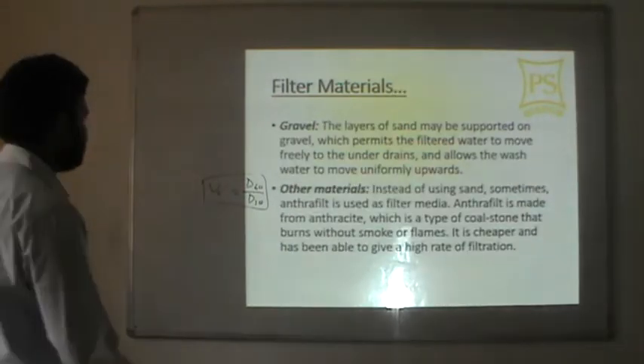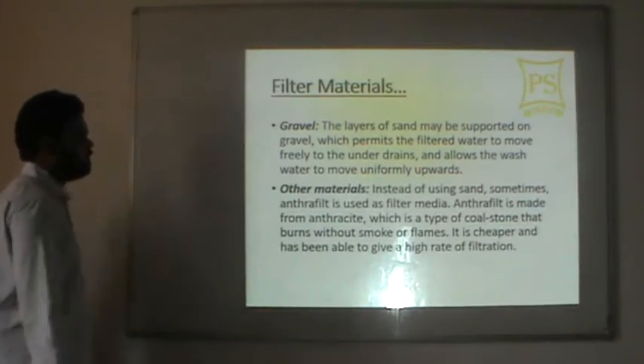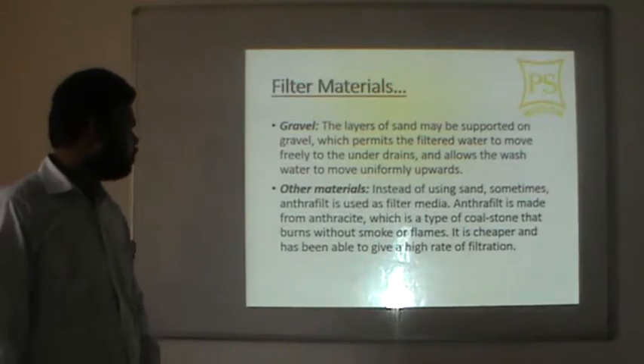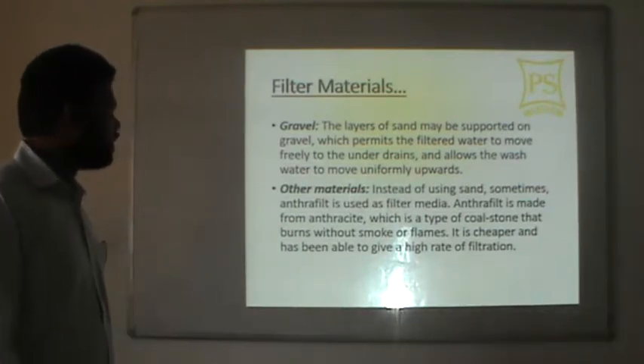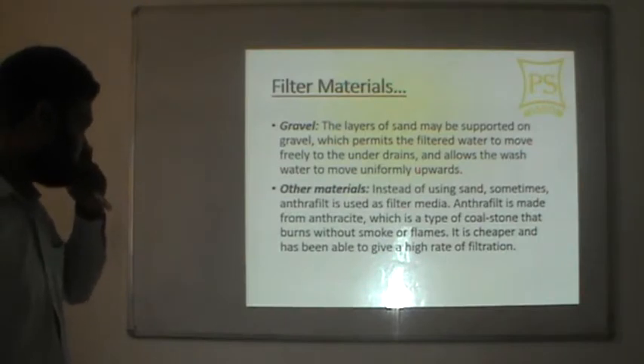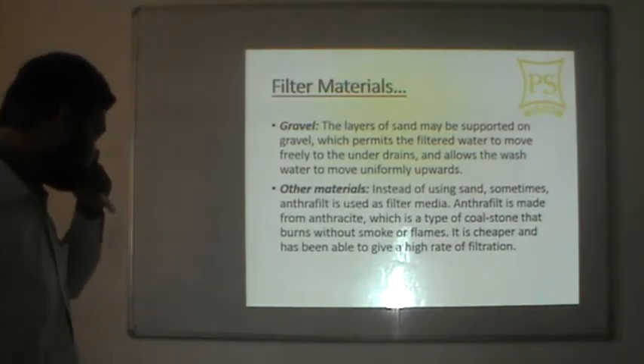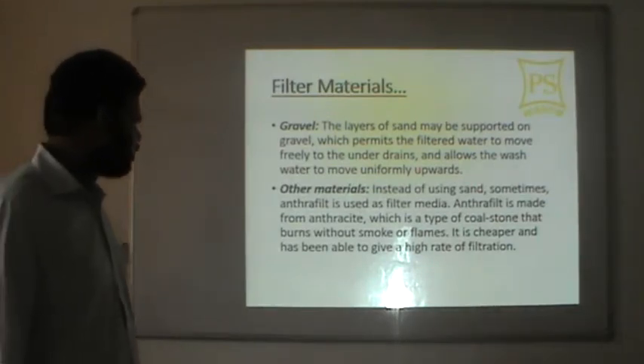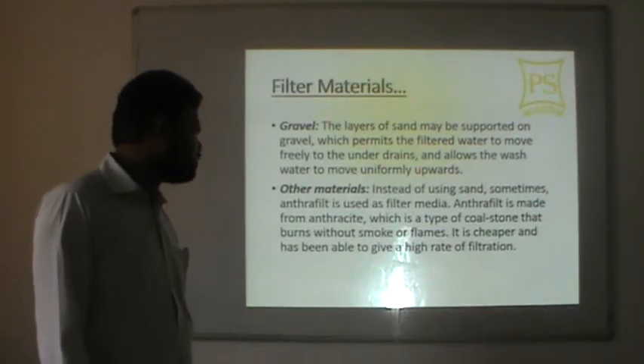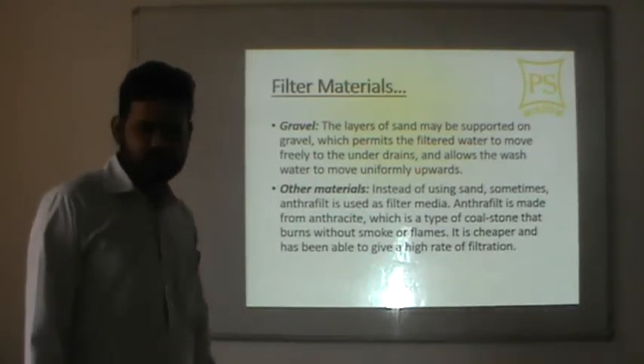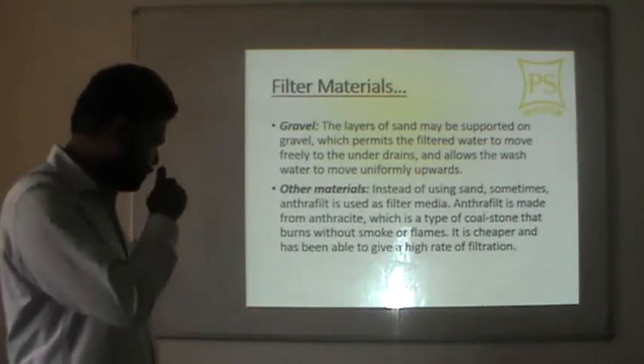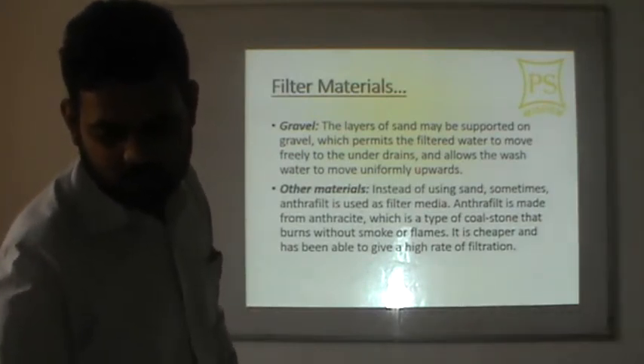The next filter material is gravel. Layers of sand may be supported on gravel, which permits filtered water to move freely to the underdrains and allows wash water to move uniformly upwards. Another filter material is anthrafilt, made of anthracite coal, which is a type of coal that burns without smoke or flames. Anthrafilter is denser and capable of providing a high rate of filtration, so it is sometimes used instead of sand.